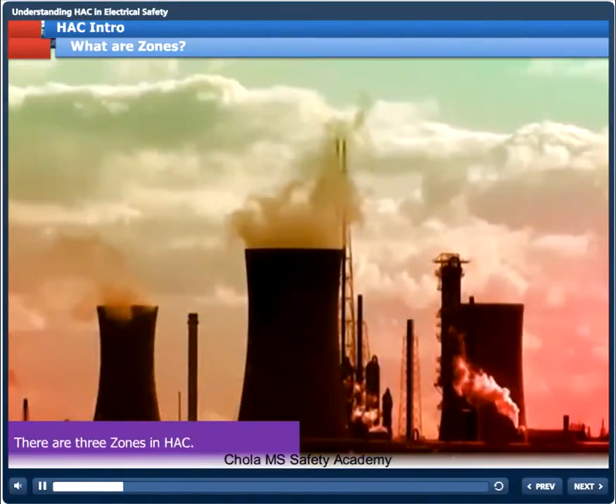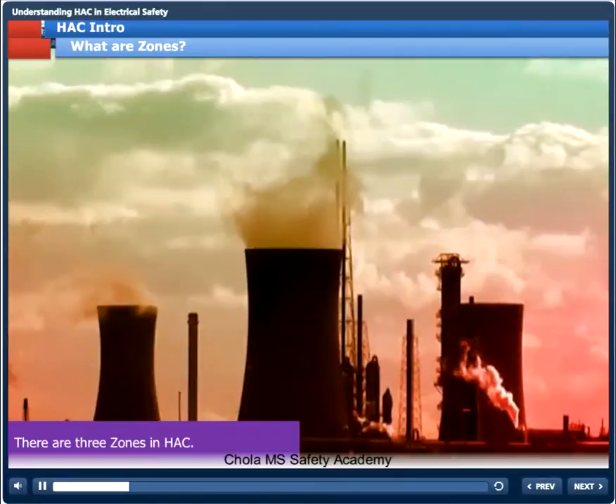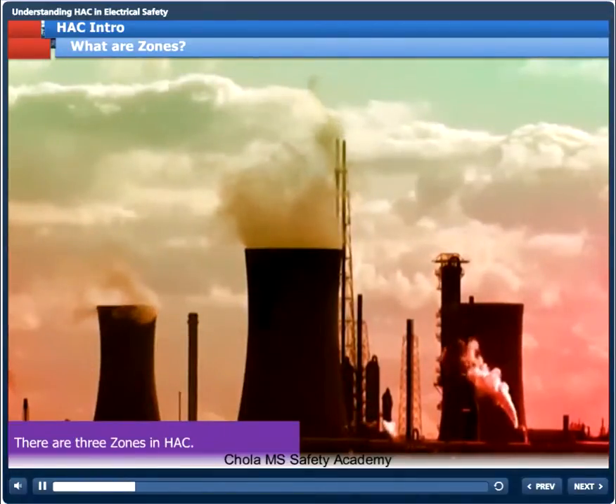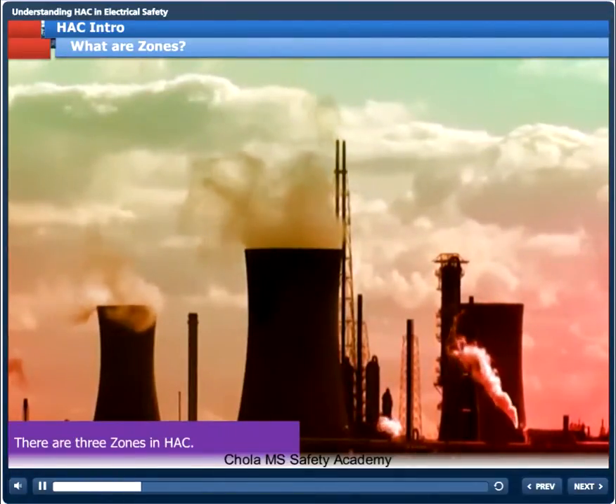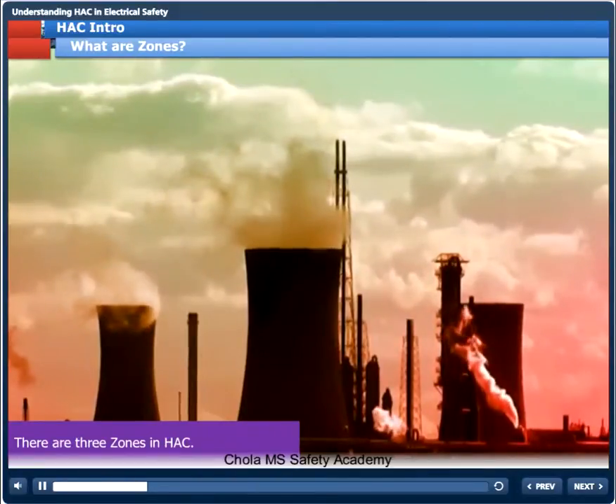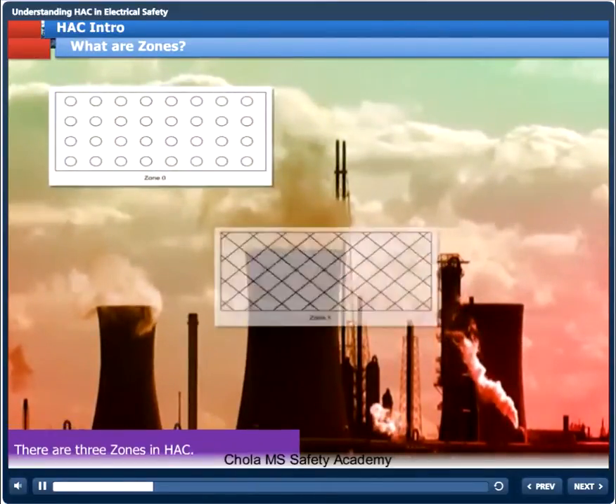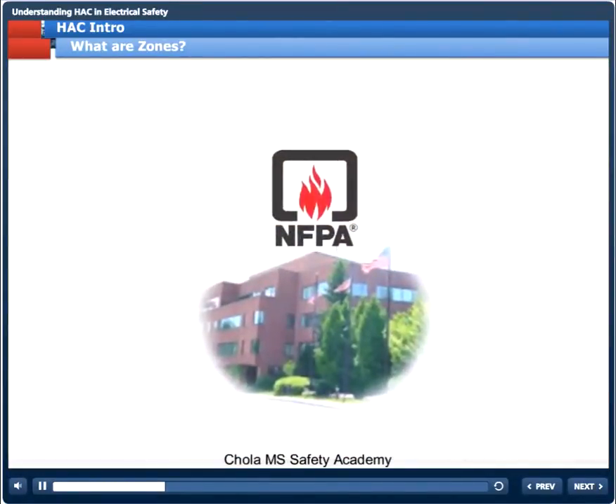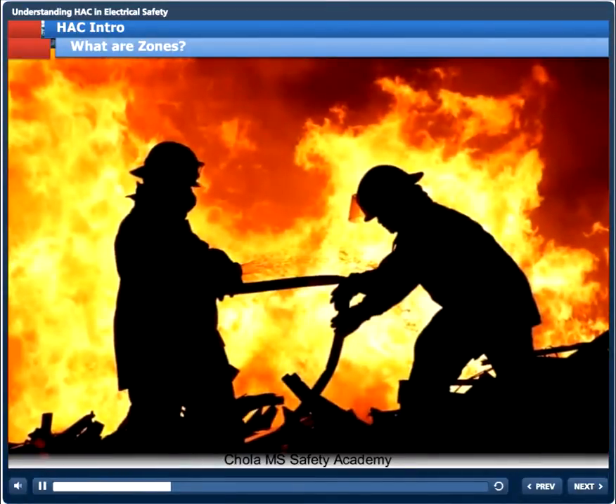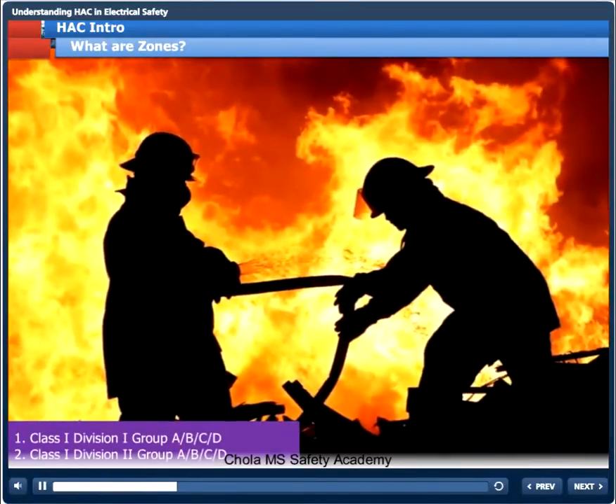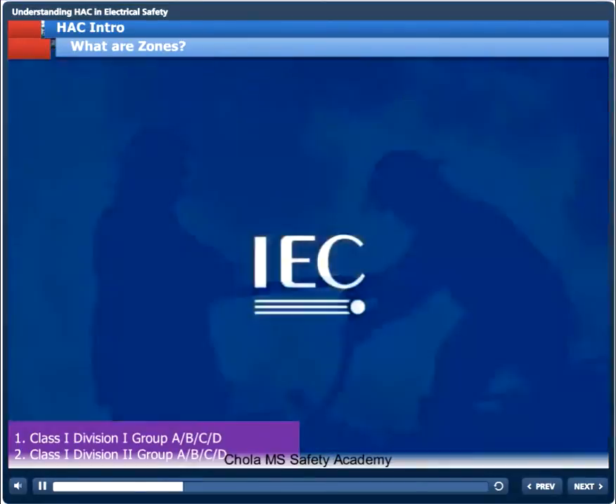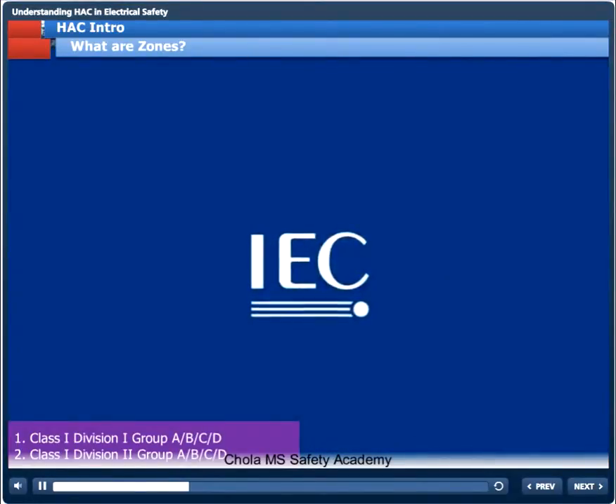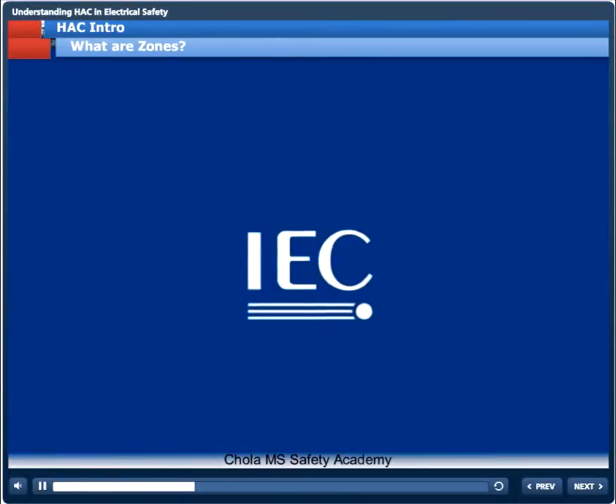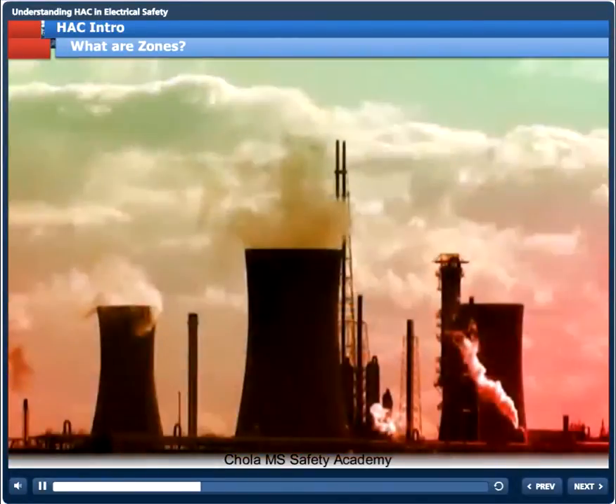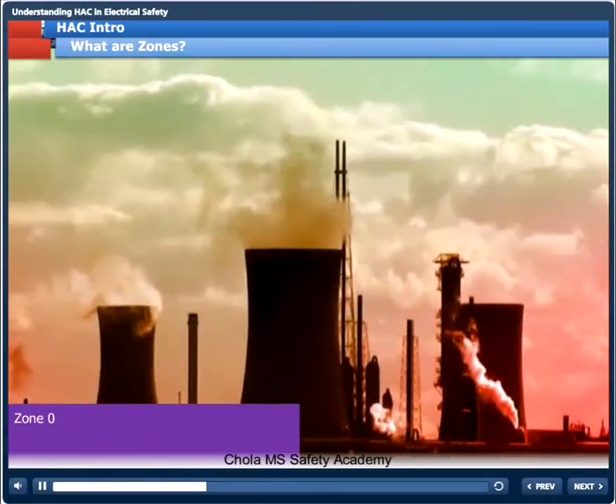There are 3 zones for hazardous area classification. The 3 zones as per IS 5572 and IEC 60079 are Zone 0, Zone 1 and Zone 2. In USA, as per NFPA standards, there are only two divisions, for example Division 1 and Division 2. We will be focusing mainly on IS or IEC method for the remainder of the discussion. We will shortly look into the nature of each zone.